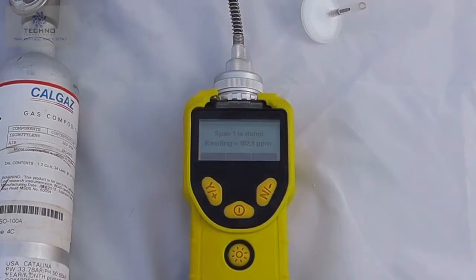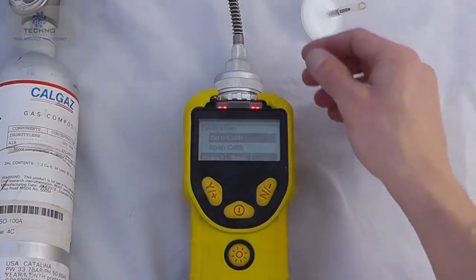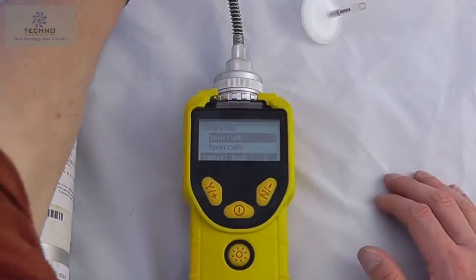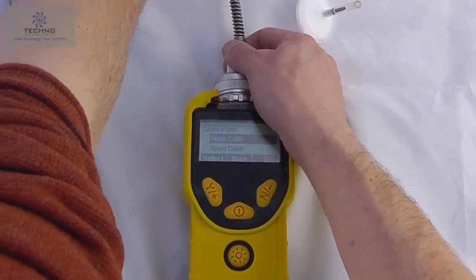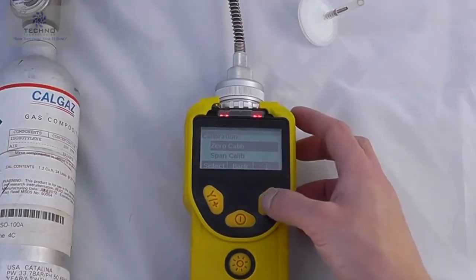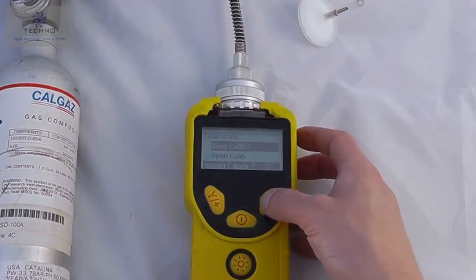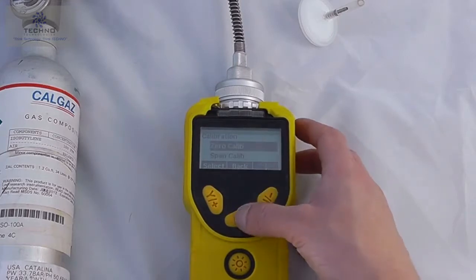And we can see we're reading 102.1 parts per million. So that span has now been successful. I'm obviously in an alarm state because I'm still showing it gas, so remove the instrument, calibration, and that's all our 2-point calibration functions done.